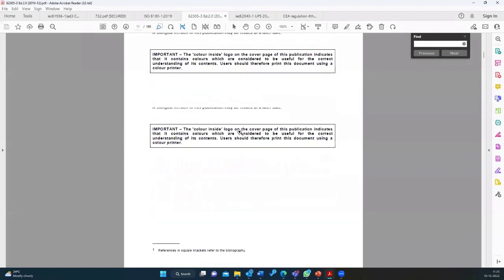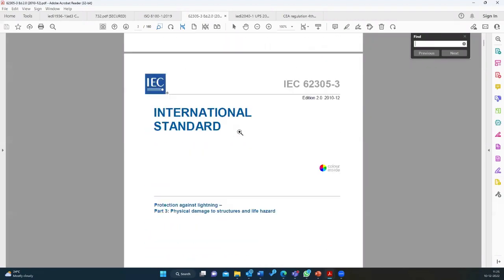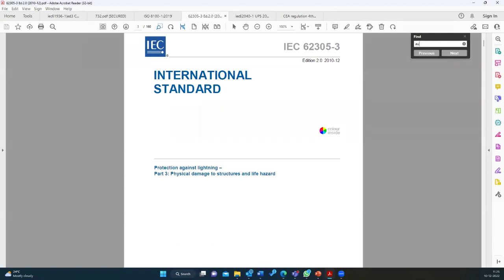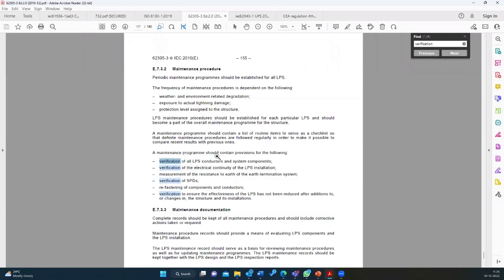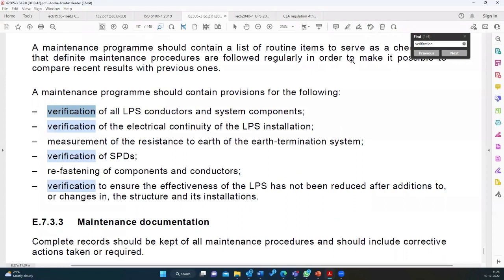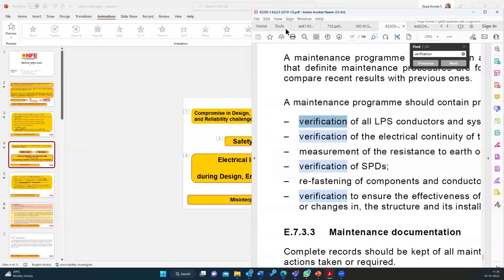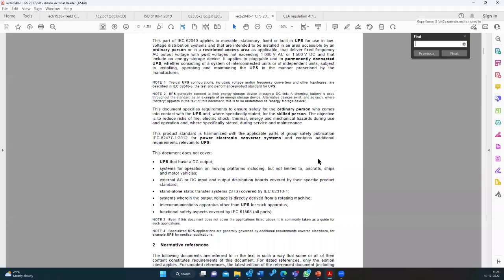Next, the lightning protection standard 62305 Part 3. I'm sure all of you know about this standard as well. Let us search for audit. Of course, no audit. Then the word verification is used in 4 places in this particular standard. A maintenance program should contain provision for the following: verification of LPS conductors and system components. So always the word which is used is verification, not audit. So when we read it, we have to be very careful in understanding this. I am also showing you the standard for UPS. Let us search the word audit. No word called audit. Verification is used 13 times in this particular standard.